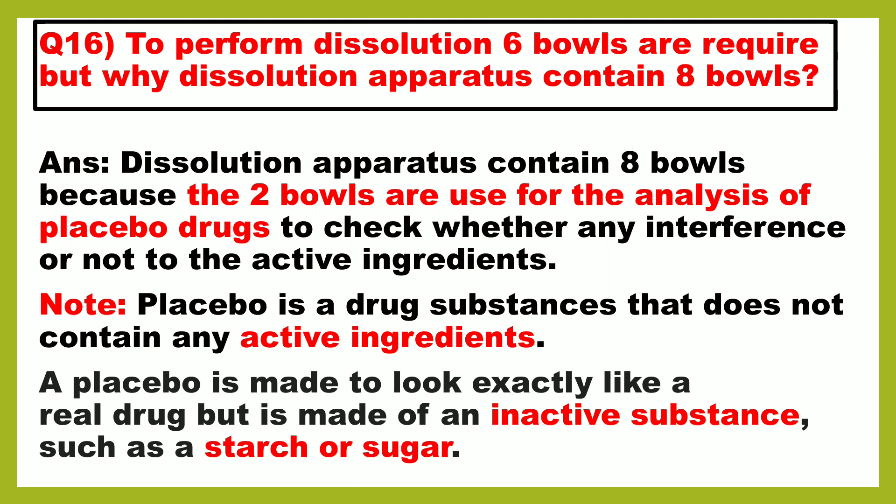Next question is: to perform dissolution, six bowls are required, but why does a dissolution apparatus contain eight bowls? The answer is that dissolution apparatus contains eight bowls because the two extra bowls are used for the analysis of placebo drug, to check whether there is interference with the active ingredients or not. A placebo is a drug substance that does not contain any active ingredients — it is made to look exactly like a real drug but is made of an inactive substance such as starch or sugar.